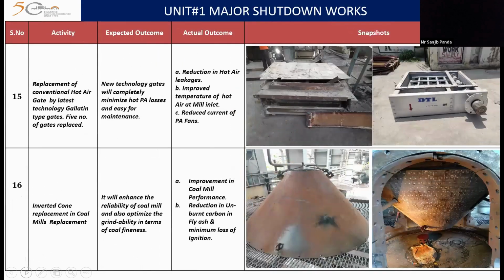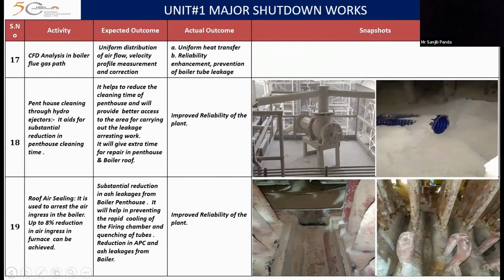Next one. Replacement of conventional hot air gate by latest technology, guillotine type gates. This is done on the boiler side. So 5 numbers of gates have been replaced, and this has been done now for both of the units. So this has helped us in reduction in hot air leakages and improve the efficiency of the boiler.